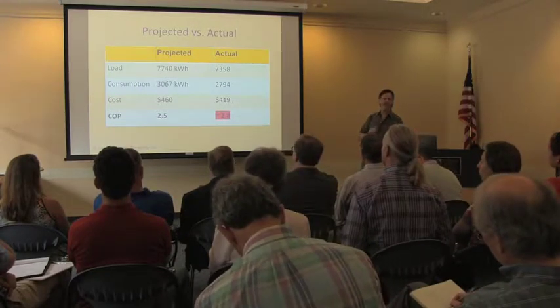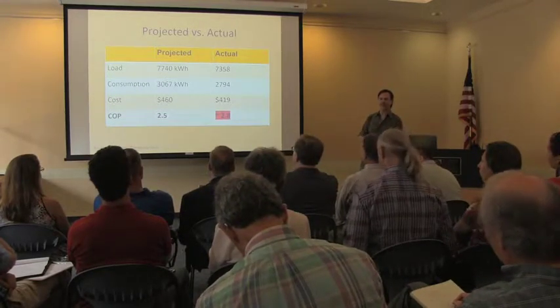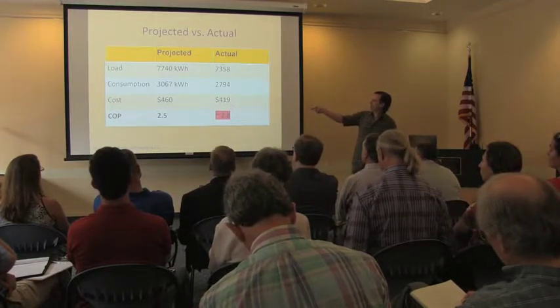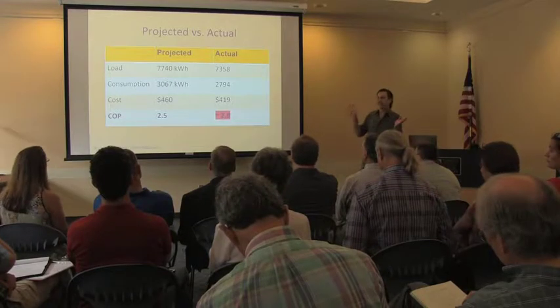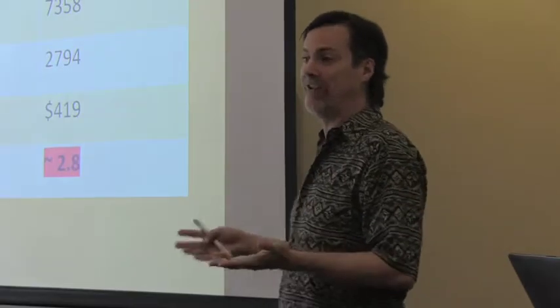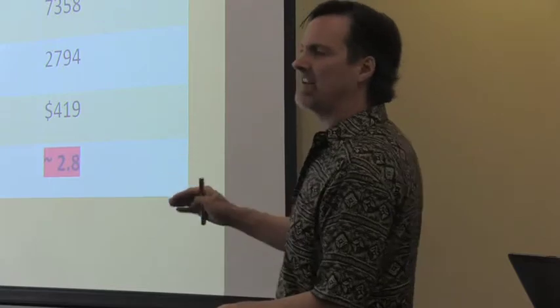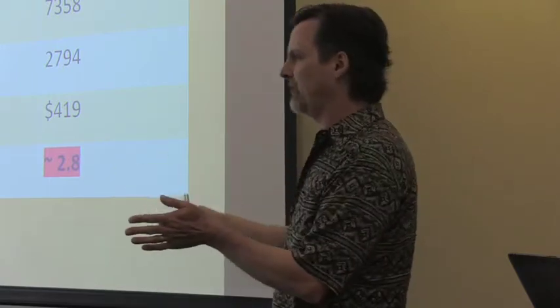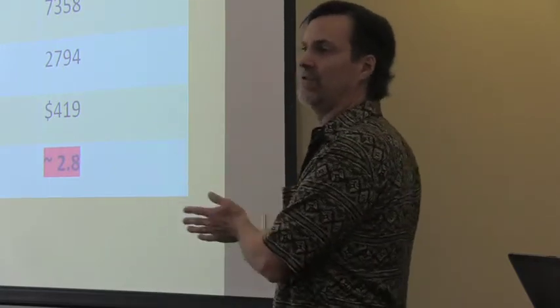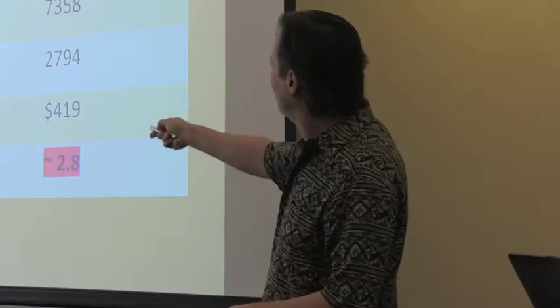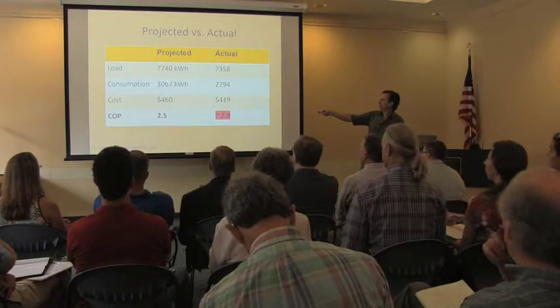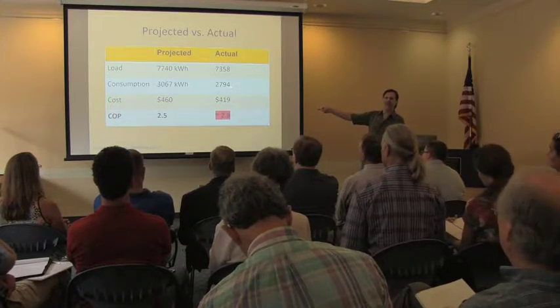Okay, not quite as high as what you get with the ground source heat pumps, but it's much, much less expensive to install. I didn't have to do any digging or drilling. And one of the things I found interesting is I did a projection, right? I'm an engineer, so I had to calculate everything in advance. I looked at the climate and I looked at the manufacturer's specs for the equipment performance at different outdoor temperatures. And I made a projection of energy consumption, about 3,000 kilowatt hours. And it actually ended up being a little less than that. So it performed a little better than I expected.